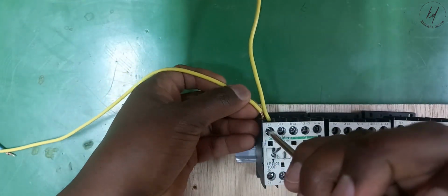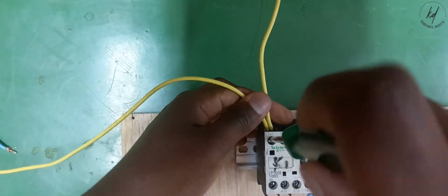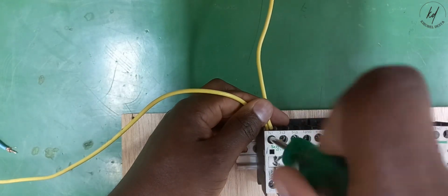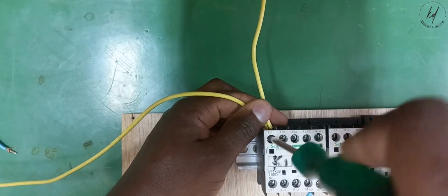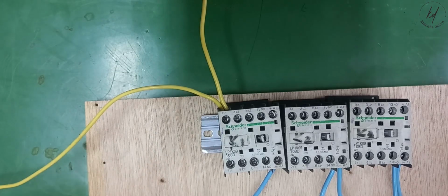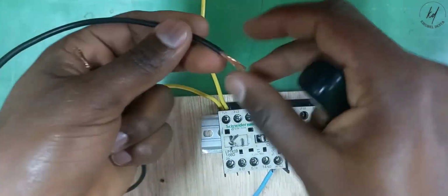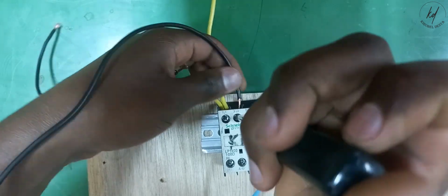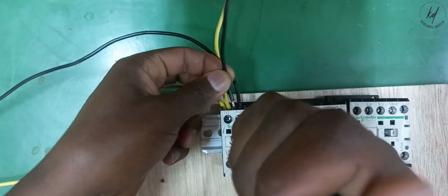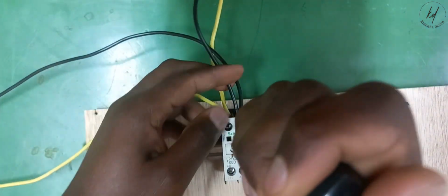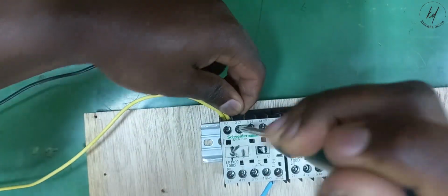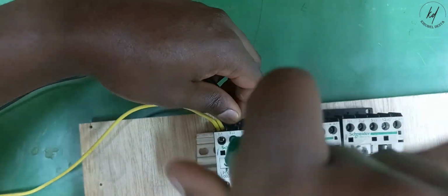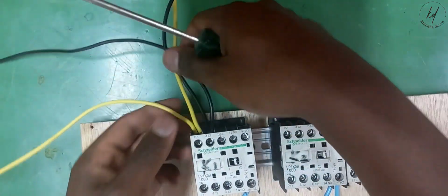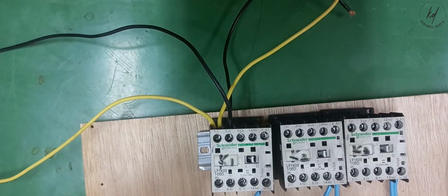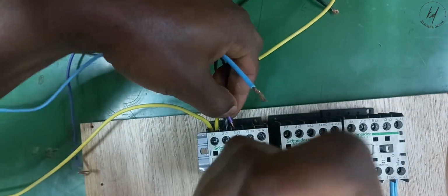5. It requires a motor with 6 leads or terminals for Delta connection. 6. For Delta connection, the supply voltage must be the same as the rated motor voltage. 7. At switching time from Star to Delta, if the motor does not reach at least 90% of its rated speed, then the current peak may be as high as in a direct online starter, which may cause harmful effects on the contactor's contacts, so it would not be reliable. 8. We may not use a Star Delta starter if the required application or load torque is more than 50% of the 3-phase induction motor's rated torque.